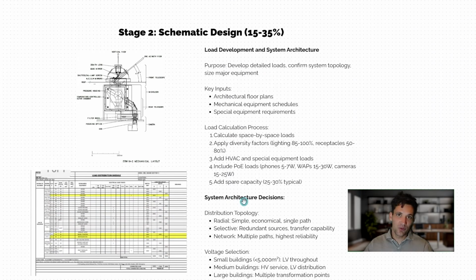So we've developed our initial technical concept, how we're going to fulfill the client requirements. And importantly, we've got that concept reviewed and approved by our client. We're going to start adding a lot more detail to this design because we roughly know what we're doing. Now we just have to start working out the exact loads, calculating everything in detail, sizing all the cables, working out where they're going to run and so forth. So the purpose of the schematic design stage is really to get detailed loads, confirm the system topology, and size all of the key major equipment like the main switchboards, the UPS, the distribution boards.